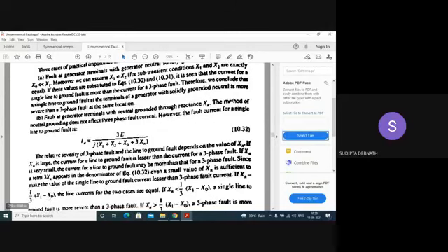Now, when XN is less than this value, you can understand that when this value decreases, this will be more severe. So for line currents, if XN is less than this value, single line to ground fault will be more severe. And when XN is greater than this value, this will be less severe, and in that case, three-phase fault current will be more severe.